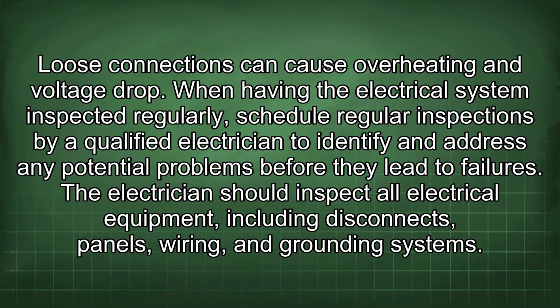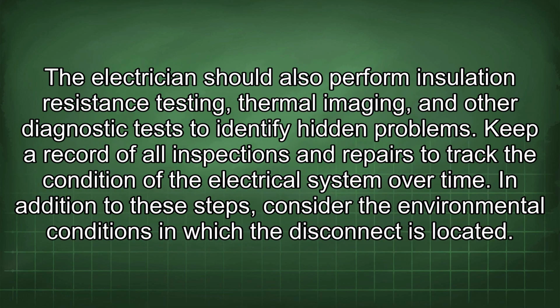When having the electrical system inspected regularly, schedule regular inspections by a qualified electrician to identify and address any potential problems before they lead to failures. The electrician should inspect all electrical equipment, including disconnects, panels, wiring, and grounding systems. The electrician should also perform insulation resistance testing, thermal imaging, and other diagnostic tests to identify hidden problems. Keep a record of all inspections and repairs to track the condition of the electrical system over time.